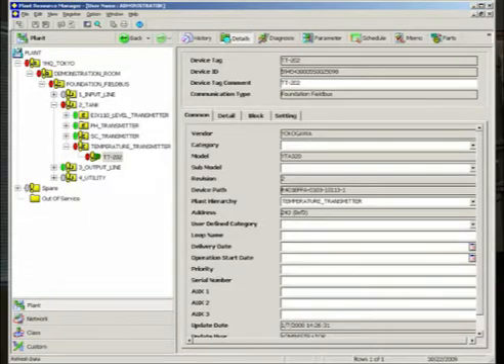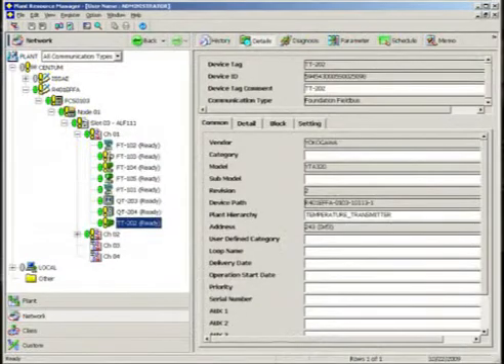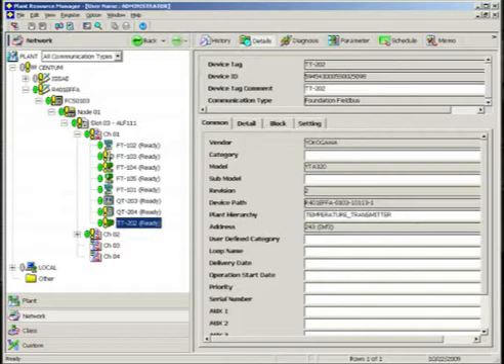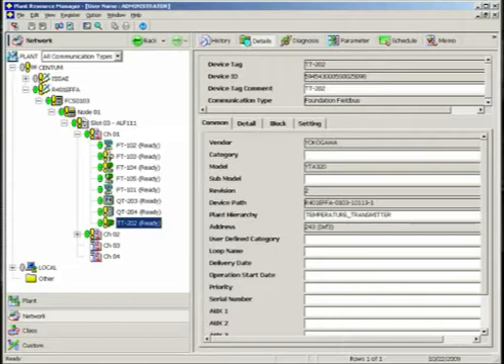Then he will launch the network view to find out how the device is electrically connected to the control network. Network view will provide information about the control network domain with DCS controller, node, card slot, and channel number related to the device.